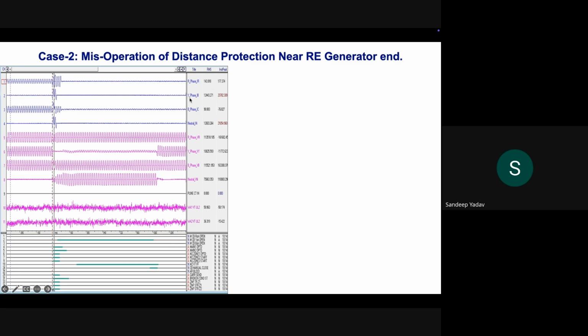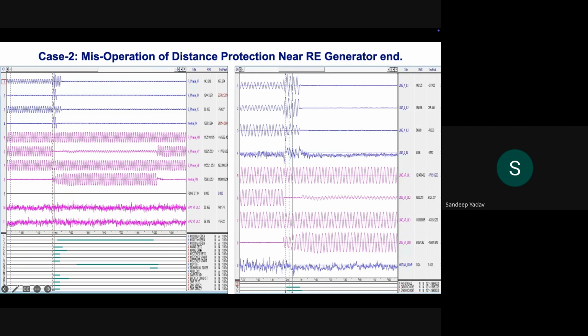So the fault current in the Y phase, which is the faulty phase, is 12,000 ampere, 12 kiloampere. If you take a look at these digital channels, it says main 1 operated and main 2 operated, which are two relays which are used on the grid side. So both the main and backup relays at the grid side have operated because there is sufficiently large current in the faulty phase, which is Y phase. So the fault current is 12 kiloampere, and both the relays which are located on the grid side have operated.